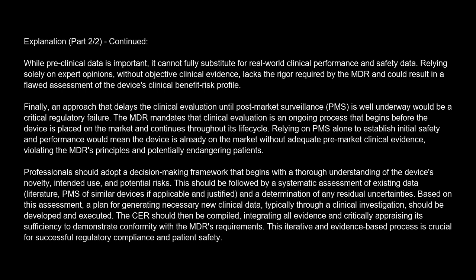Professionals should adopt a decision-making framework that begins with a thorough understanding of the device's novelty, intended use, and potential risks. This should be followed by a systematic assessment of existing data, literature, PMS of similar devices if applicable and justified, and a determination of any residual uncertainties. Based on this assessment, a plan for generating necessary new clinical data, typically through a clinical investigation, should be developed and executed. The CER should then be compiled, integrating all evidence and critically appraising its sufficiency to demonstrate conformity with the MDR's requirements. This iterative and evidence-based process is crucial for successful regulatory compliance and patient safety.